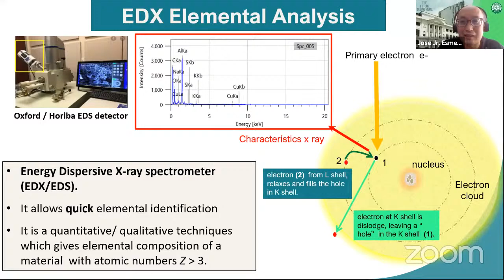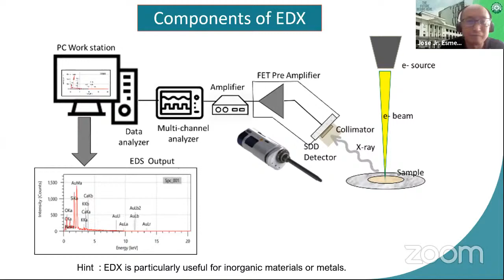This is the structure of an EDS, a simplified diagram. So you have an electron source, and that beam hits a sample, as I said before. Because of the electron-matter interaction that produces X-rays, and these X-rays are collected by a detector. The signal from this detector is amplified and processed by a computer, and then you get an EDS spectrum. So this is particularly useful for inorganic materials and the like, metals, something like that.